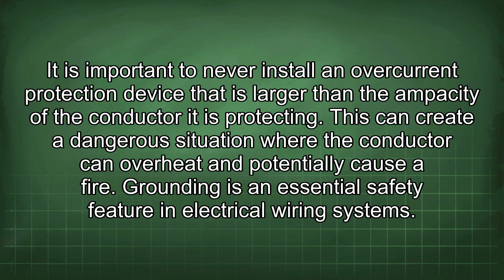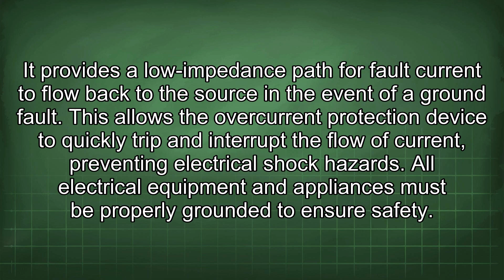Grounding is an essential safety feature in electrical wiring systems. It provides a low impedance path for fault current to flow back to the source in the event of a ground fault. This allows the overcurrent protection device to quickly trip and interrupt the flow of current, preventing electrical shock hazards. All electrical equipment and appliances must be properly grounded to ensure safety.